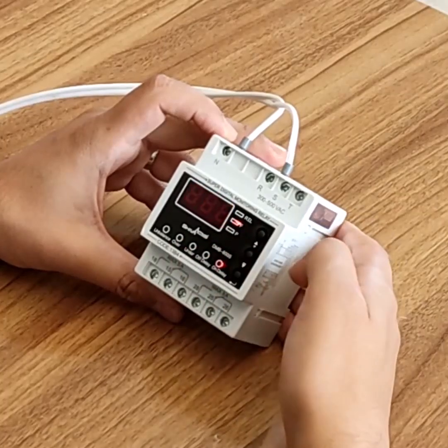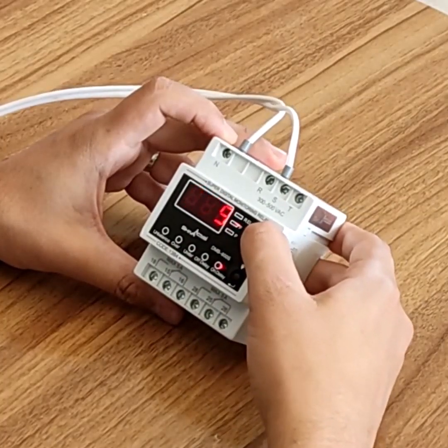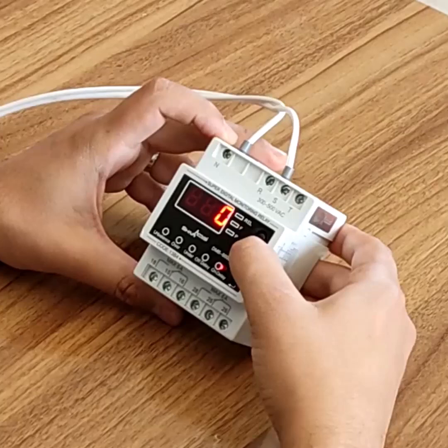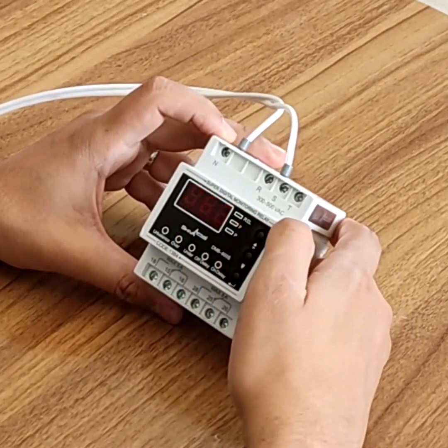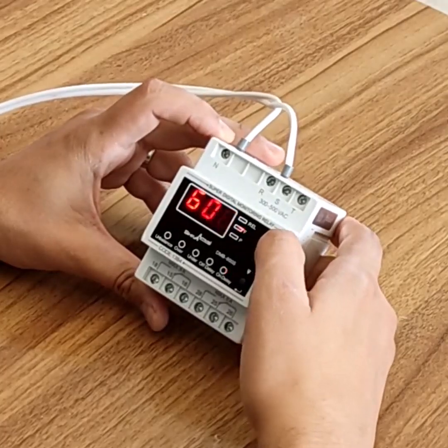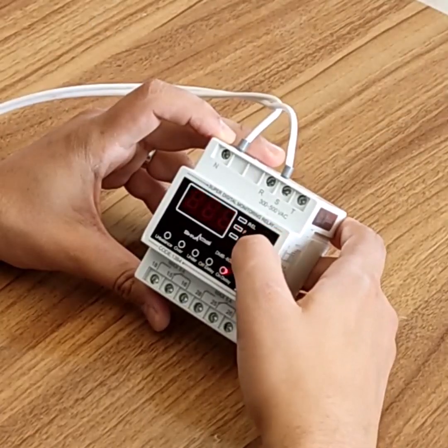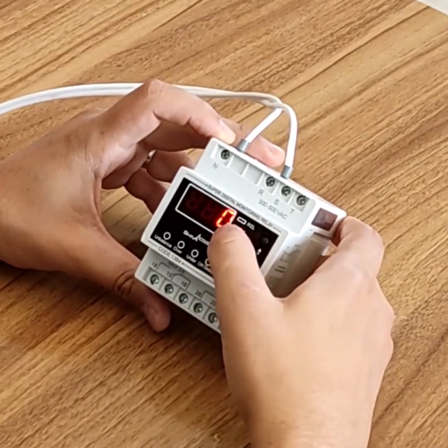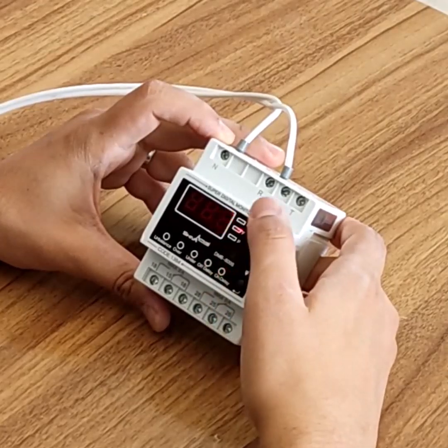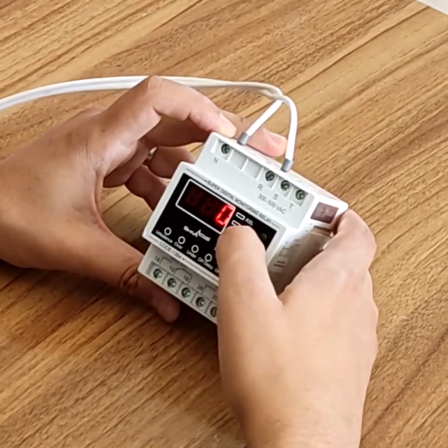the time that allows the control circuit to be activated after the fault is clear. You can consider a number between 0 and 600 seconds. If you set it to 0, after the error is resolved, you can run the command circuit immediately. If you set it to 10 minutes, after the error is resolved, you can run the command circuit.